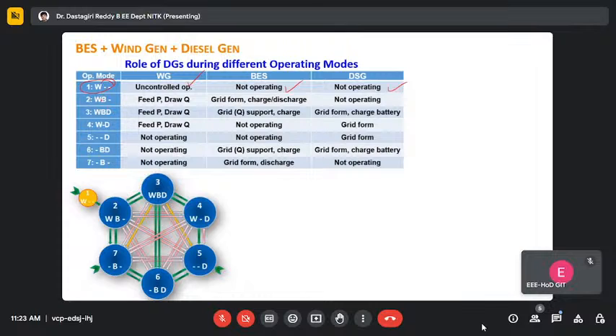Now if wind and battery are there, what will happen? Wind will be in PQ mode, battery will be in grid forming mode, either charging or discharging, diesel is not operating. Wind will go into PQ mode, BES will support the grid and support the wind to bring it in. After that, the diesel generator will take the grid forming mode, and this will go into PQ mode after making the transition, or it can stay with only Q control, either charging or discharging.